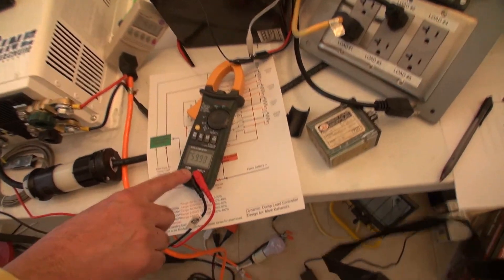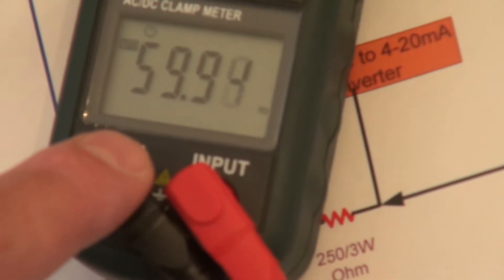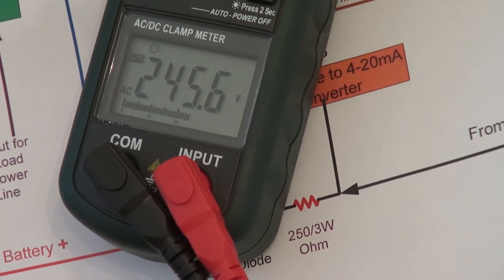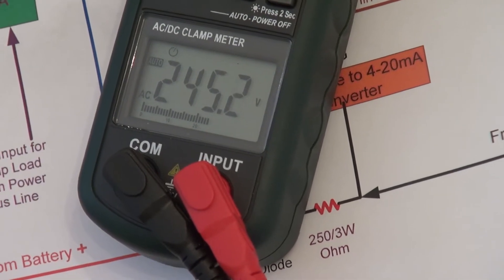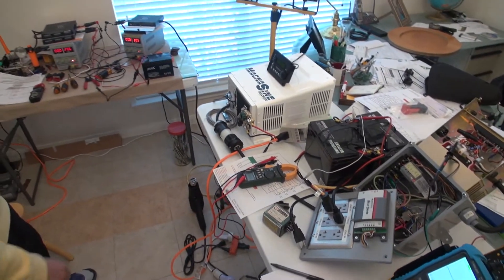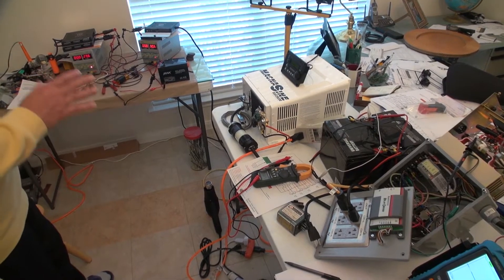Yes, the frequency is almost 60 Hz, 59.9 Hz right there. And the voltages, let's take a look at the voltages. It's 246 volts. So they have correct voltage and correct frequency. They should come on not later than five minutes. It's pretty much, I tried it many times.